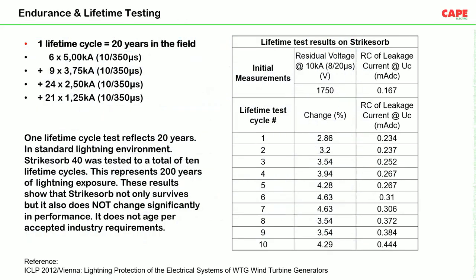So the endurance and lifetime testing of an SPD. Normally, we have taken an example of Strikesorb 40 and it was tested with 10 lifetime cycles. What is a lifetime cycle? One lifetime cycle is equivalent to 20 years of operation in the field. So how do we test one lifetime cycle? An SPD is given 6 numbers of 5 kiloampere 10/350 impulse, 9 numbers of 3.75 kiloampere 10/350 impulse, 24 numbers of 2.5 kA 10/350 impulse, and 21 numbers of 1.25 kA 10/350 impulse. This constitutes one lifetime cycle.